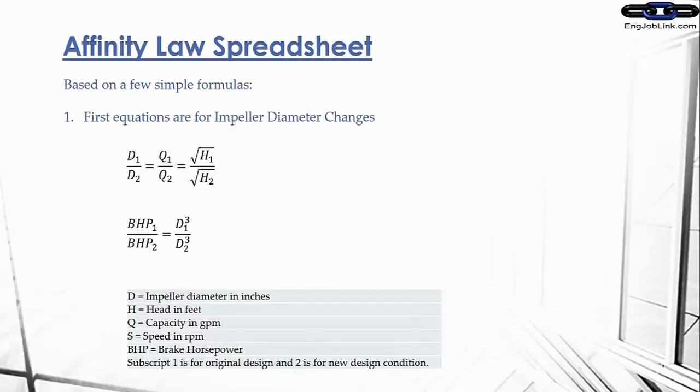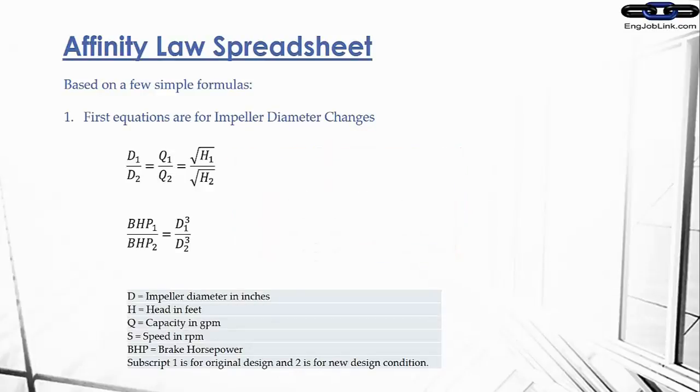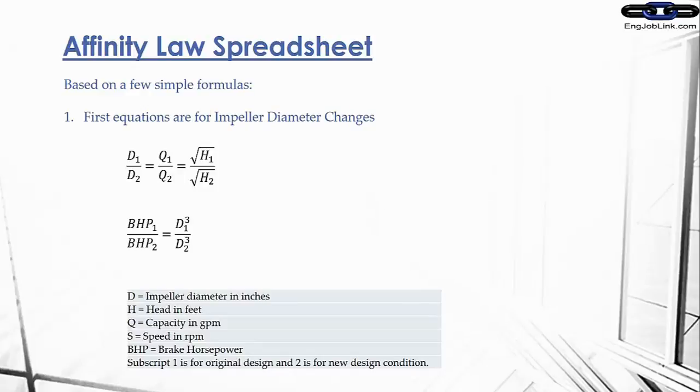You really don't have to have a spreadsheet for this; they're pretty simple formulas. But I have got a quick and dirty spreadsheet set up and I wanted to offer that to you. You can have it for free if you come to Engineering Job Link, which would be engjoblink.com, and you can download that spreadsheet for free. Basically, with the pump affinity laws you've got a couple of different sets of equations. Some of them deal with impeller diameter change, and the affinity laws are good for just small diameter changes, not large changes. The other set deals with speed change, so you want to know what flow you're going to have if you reduce the speed of your pump or increase it.